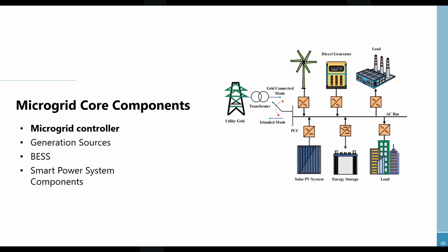As soon as the utility loses power, the system needs to switch instantly to island mode and disconnect from the grid so that we don't end up back feeding power onto the grid, which is a safety issue for the utility itself. The linemen going out to repair whatever went on, making changes to the switching and protection of the system, need to be able to do that without being electrocuted. So that switch-off mode is really key for a microgrid, and that's what puts you into island mode. Your system is going to operate like its own little island.